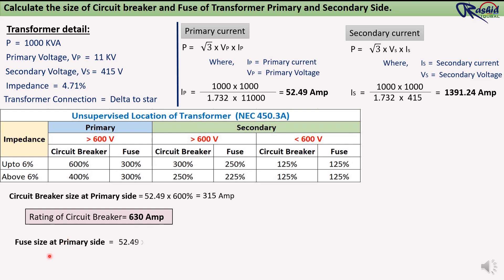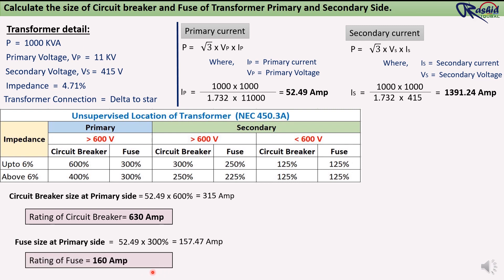For fuse size calculation, we multiply 300% by the primary current: 52.49 × 300% = 157.47 ampere. Since a 157 ampere fuse is not available in the market, we use a 160 ampere fuse, which is available. So we select the 160 ampere fuse.